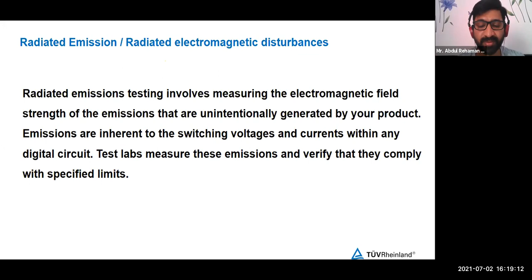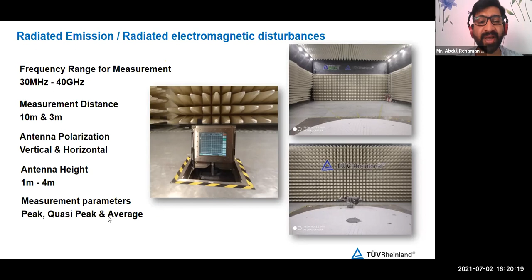Radiated emission is usually performed for the European market from 30 megahertz to 6 gigahertz. When you go for the US market, it is performed up to 40 gigahertz, depending on the internal frequency of the product. Usually the testing is performed at 10-meter distance and 3-meter distance. In this setup, the white one is a turntable which rotates from 0 to 360 degrees, and we have an antenna mast which varies from 1 to 4 meters. So the emissions are captured at all angles and all heights of the product. Even here we measure peak, quasi-peak and average data.